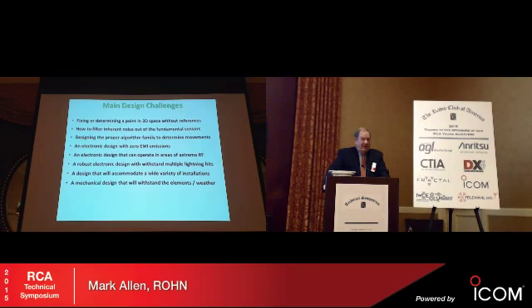So the question is, how accurate is it? We can measure reliably down to probably about 1/4 of an inch of movement, which is plenty sufficient for what we're trying to measure. And that's in all 3 axes. Okay, the other problem was, if you're going to take one of these and mount it on top of my tower in amongst all those cell phone antennas and stuff, what kind of emissions can it create on its own?